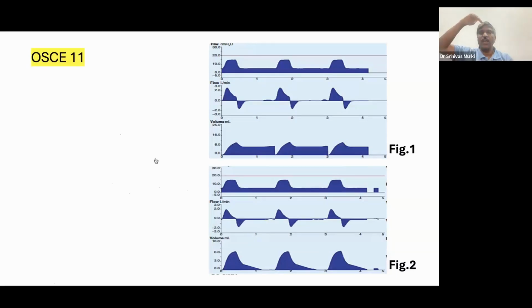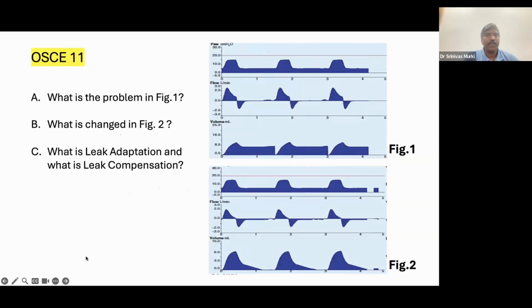Now same thing, if you are having expiratory asynchrony, which is the flow is not able to come down to zero. Suppose you have a leak and you are not able to reach 80% down from the peak for termination. So the machine will automatically titrate for the leak and bring it above, so that termination sensitivity also happens. So this is inbuilt. So you don't have to adjust for leak adaptation, but leak compensation you have to activate in some of the machines.